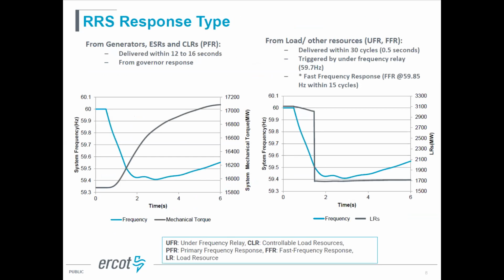The responsive reserve can come from two different types of resources. The first one is generators. The second is controllable load resources. All these batteries can provide the governor type of response. So for any of these resources online, ERCOT requires them to have this governor function enabled, and they can provide this kind of proportional response. Usually they deliver the response within 12 to 16 seconds as the frequency drops.